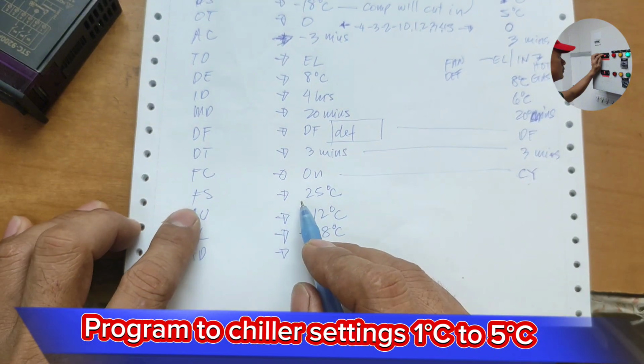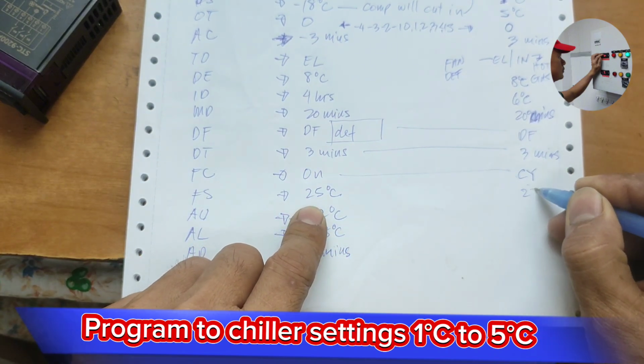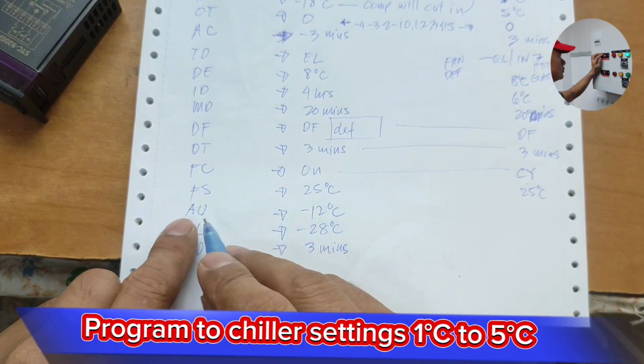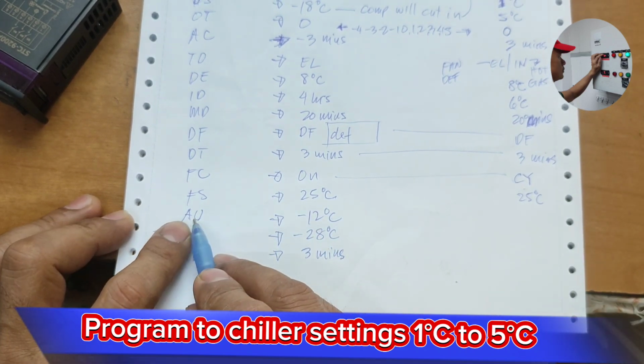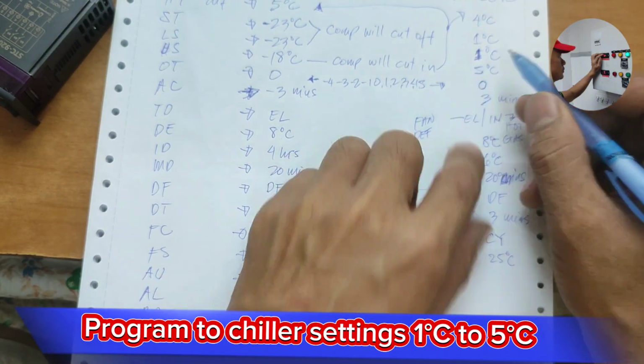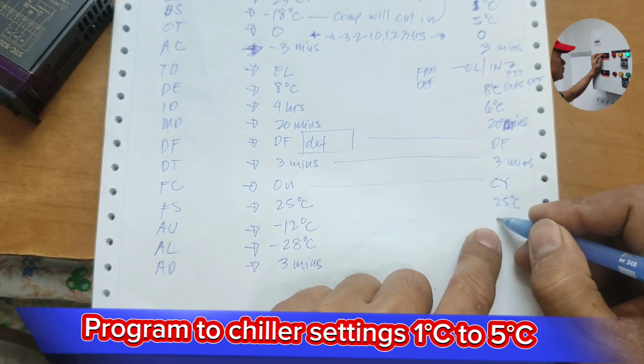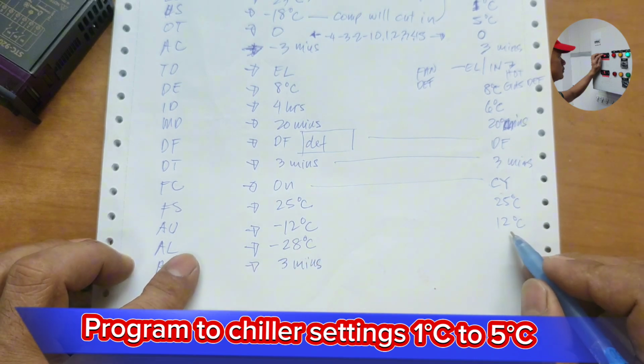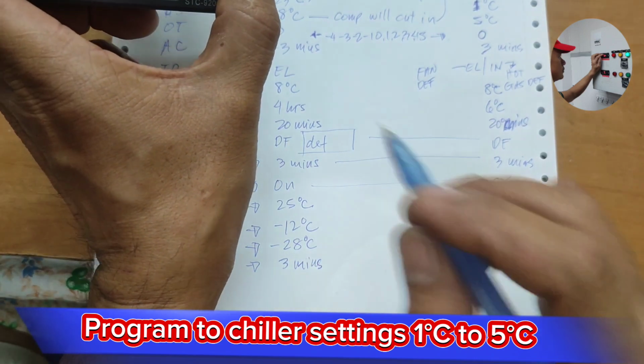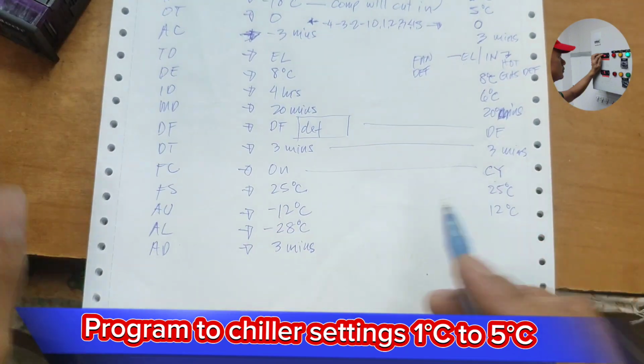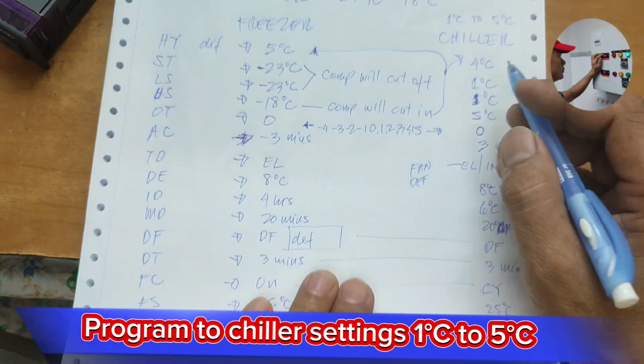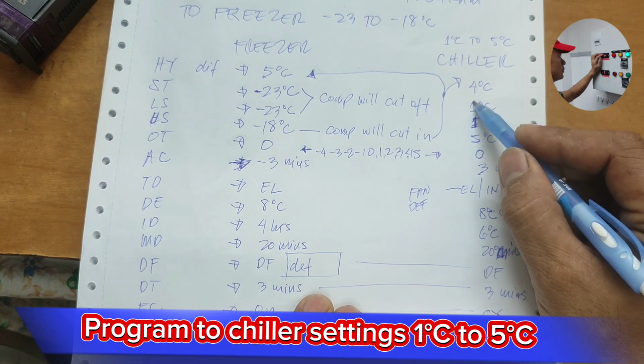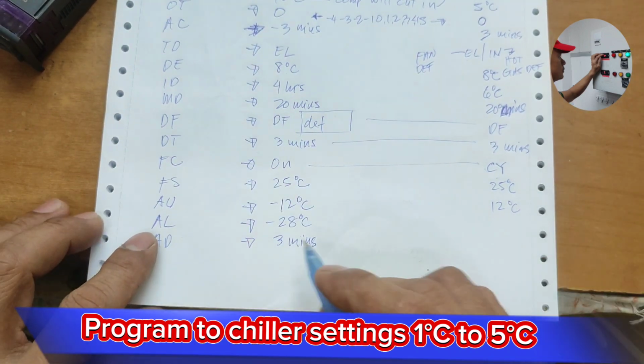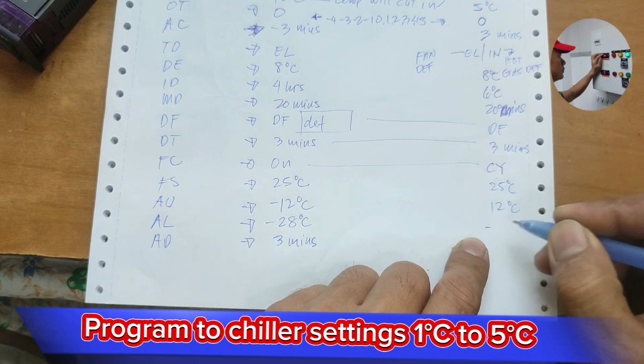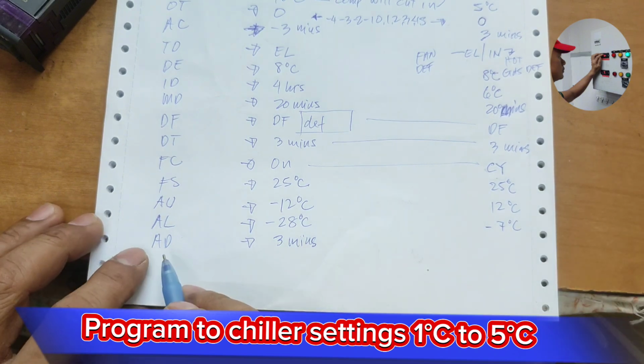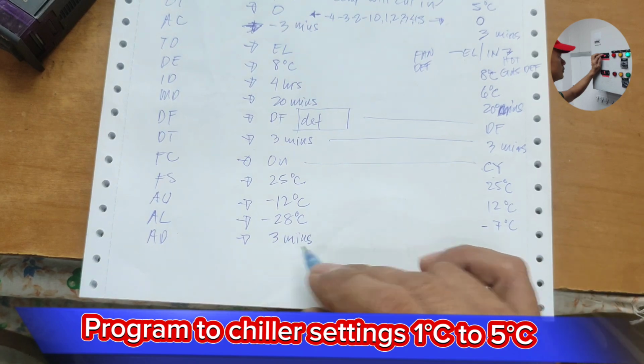And then for fan stop temperature, same, use 25°C. And for the AU, okay, our highest temperature here is 5°C, just add 7, so I'm going to put 12°C here, so this will be my highest temperature. And take a look, we're encountering an HA alarm. And for the lowest temperature alarm, we have 1°C here as our lowest temperature. So we just subtract 8, so we go to negative 7°C, and we're going to delay the activation of these two values to 3 minutes only.